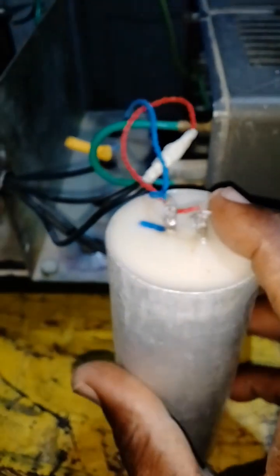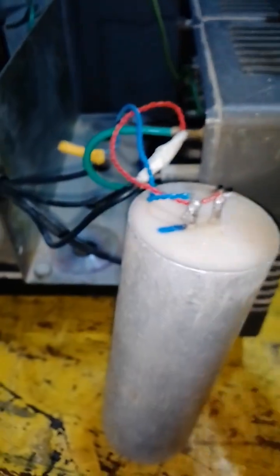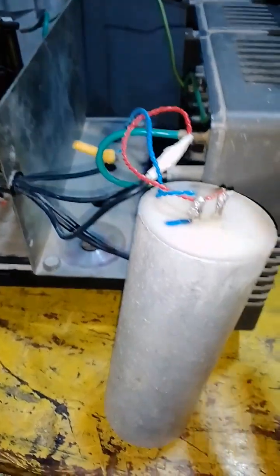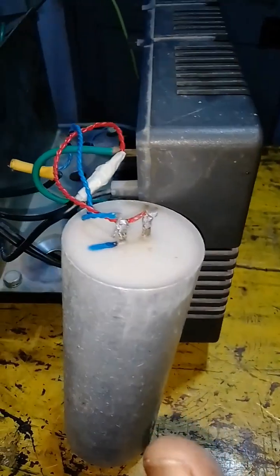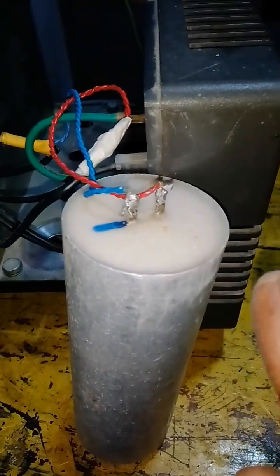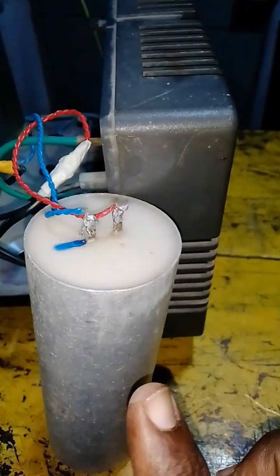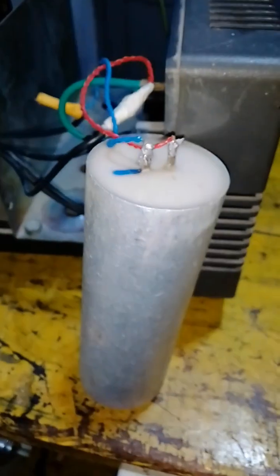It's written here that it's supposed to show 20 UF. That shows this capacitor is working, and if so, the stabilizer is supposed to work. But if the UF reading is not there, or is lesser than 20 UF, it means it cannot power this coil, so the stabilizer will not work and there won't be any output voltage. That's one of the major problems of this type of stabilizer.